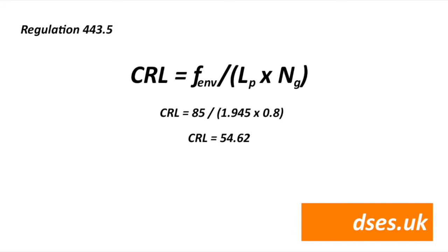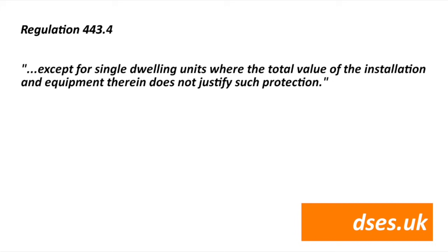But anyway, if you don't know the cabling distances to accurately use this formula to get out of installing surge protection, then to comply with 18th edition you're going to be fitting SPDs as a matter of course in commercial installations. Why commercial installations? Well, there is a silver lining for domestic applications. Going back to Regulation 443.4, a get-out clause is given for single dwelling units where the total value of the installation and equipment therein does not justify such protection. So you can sidestep surge protection when working on a single house, flat, apartment, etc.